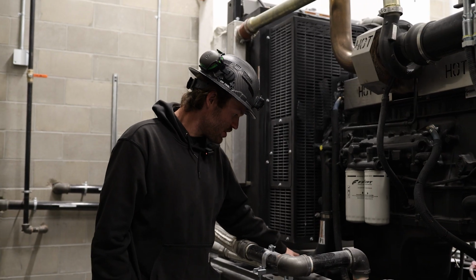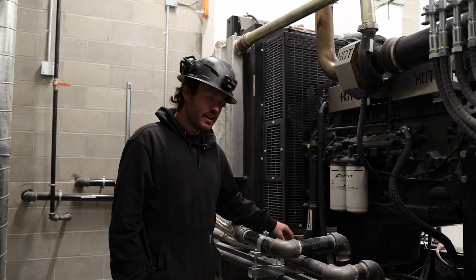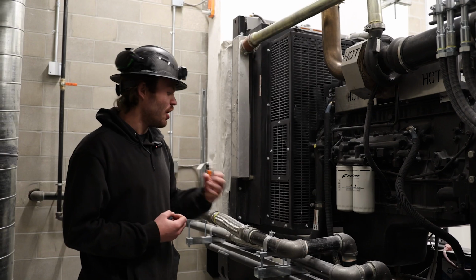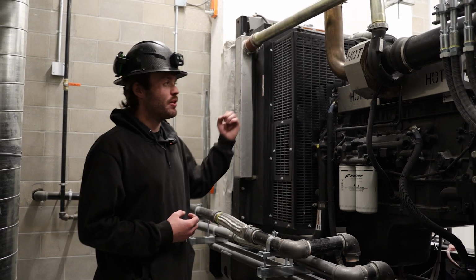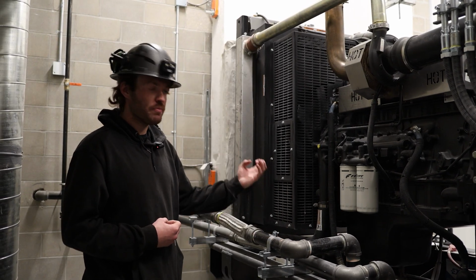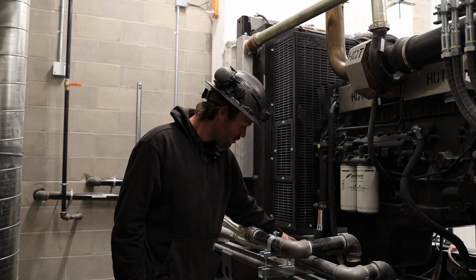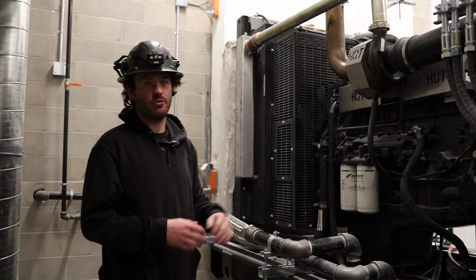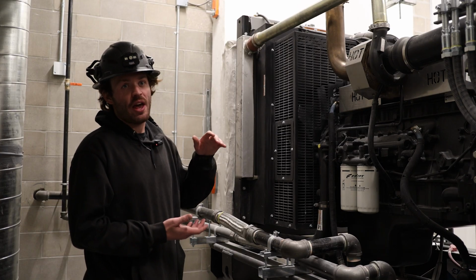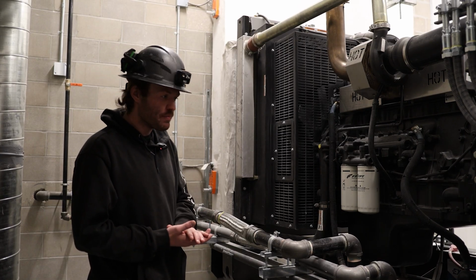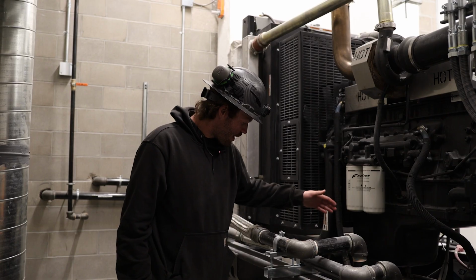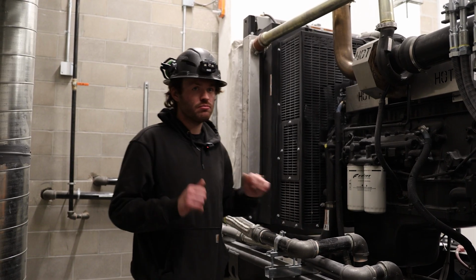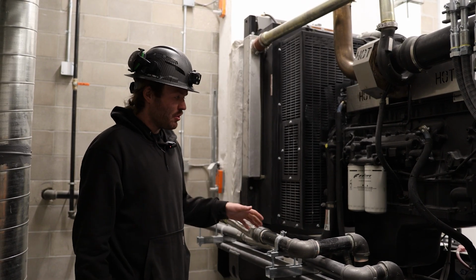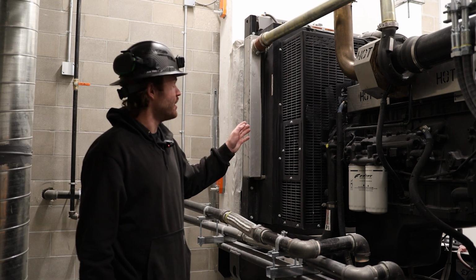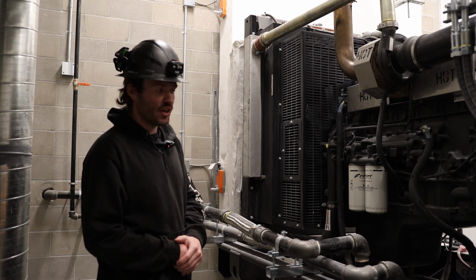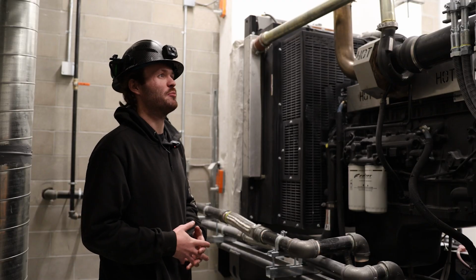Our coolant expansion tank is mounted down low. Any excess coolant when it expands and gets hot will be pushed into the expansion tank. When the unit cools, it'll draw back in that coolant. The level in the tank will constantly fluctuate. Currently it's at about half, but if it were to get hot, you'd see that level increase, and when it cooled down, possibly even decrease. There's a high level and a low level. As long as it's always above the low level, you're good to go. If it gets below that, it runs the risk of possibly sucking air into our cooling system. Not the end of the world, but we avoid it as best as possible.